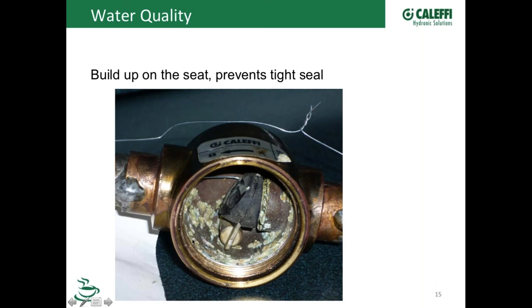Yeah, I know there's a lot of those combis, and I shouldn't say a lot, but there are combi systems still being installed out there where they're using the same domestic hot water to go through an air handler like the old Apollo systems. They're still available, so we do see valves being used in combi systems, and that's what I suspect here when I see that kind of mineral buildup.